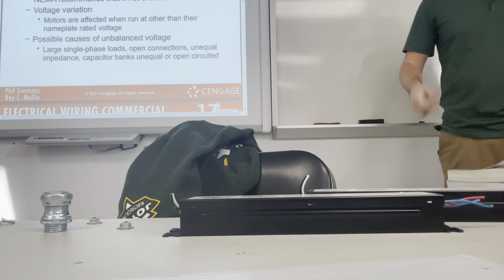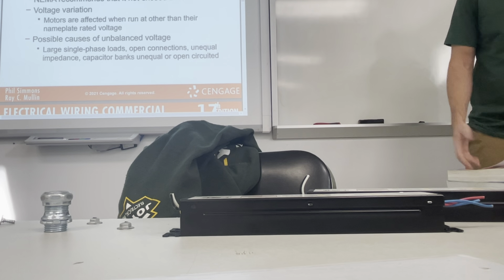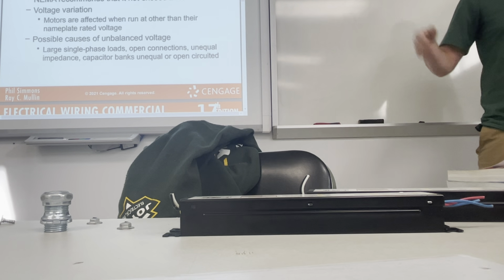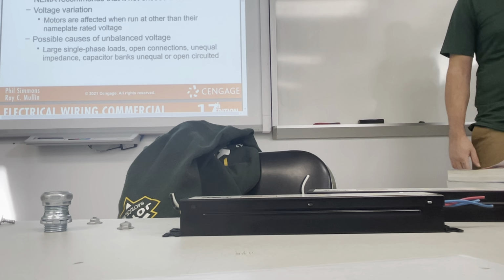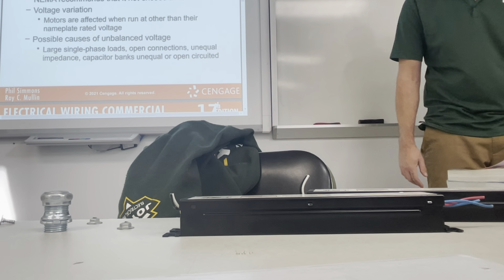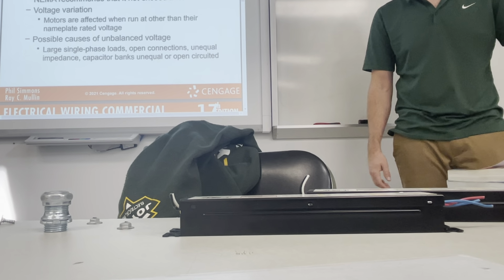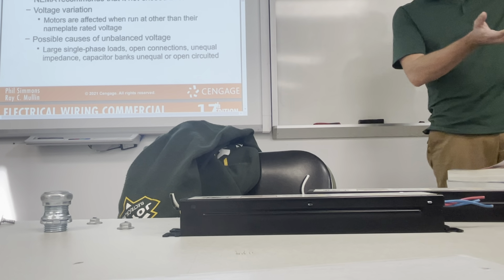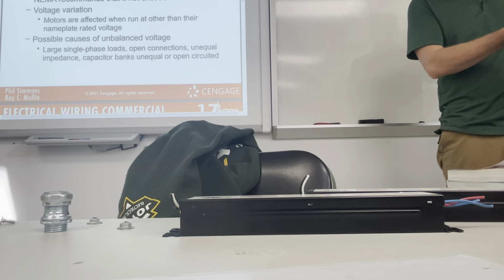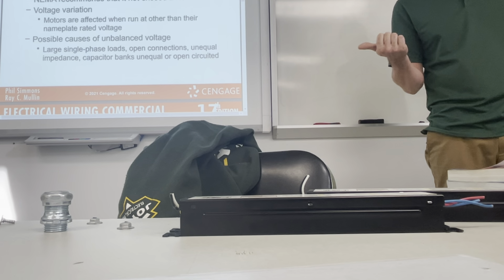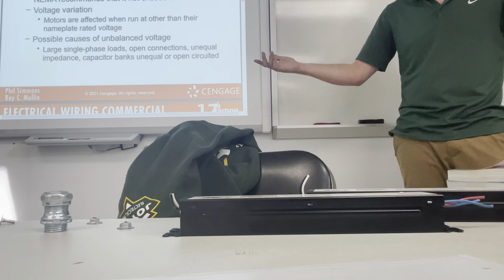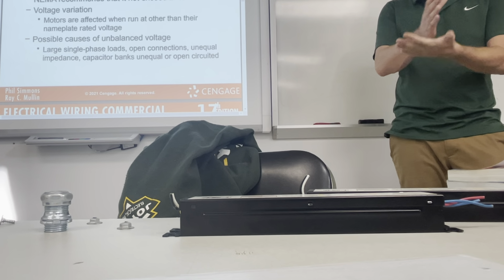Shit, I only bought black wire. Fuck. Oh well, I have to run a bunch of 20 amp circuits. I'll just run all black and put those breakers in the black terminal, which is fine, it's code. But what happens if you have 20 breakers on there, it's all black conductor coming off, and then you have one 3-phase breaker feeding a 3-phase motor? Do you think all legs are going to be even now?